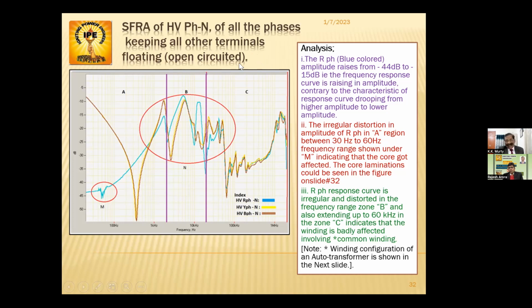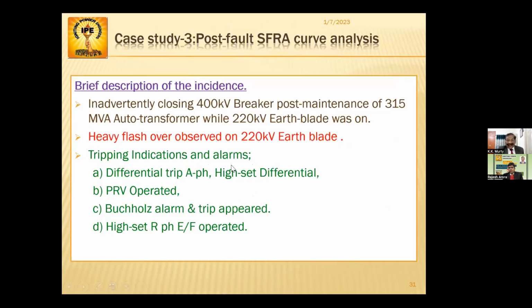So you can see the curve here. The indication shows differential A phase. Okay, A phase in ABC convention, of course. Differential A phase, high set differential, PRV operated, Buchholz alarm and trip appeared, and high set R phase earth fault operated. Here it is A phase because of the convention used in the differential relay, and most of the operators say R phase earth fault for the relays. In general convention, we have R phase, Y phase, B phase. That's what we say. So one should not get confused because of this nomenclature of the phases.